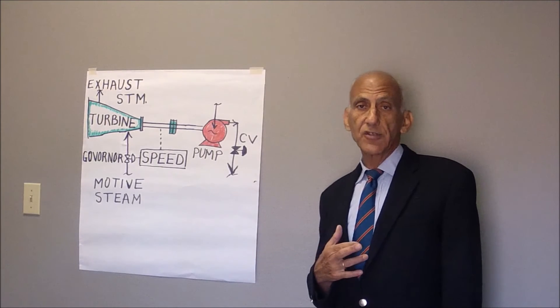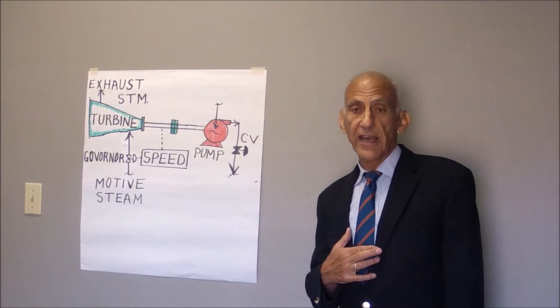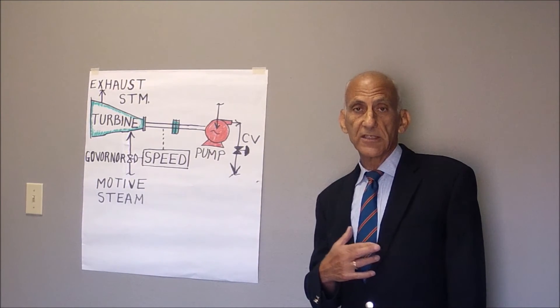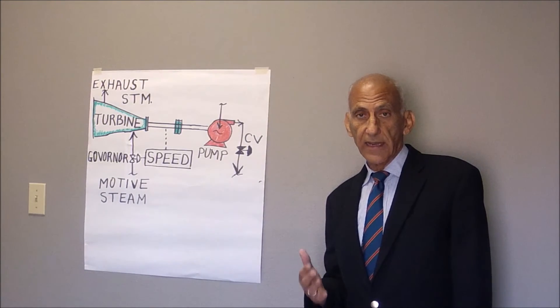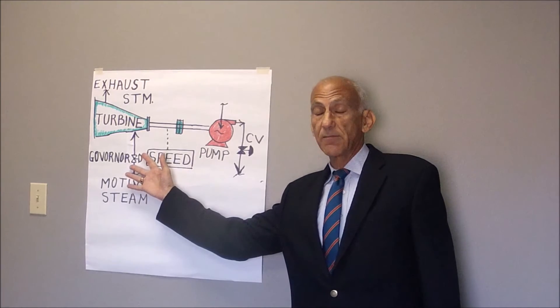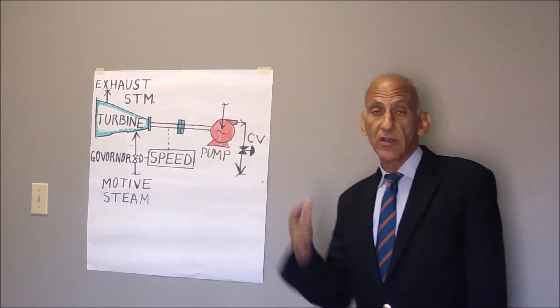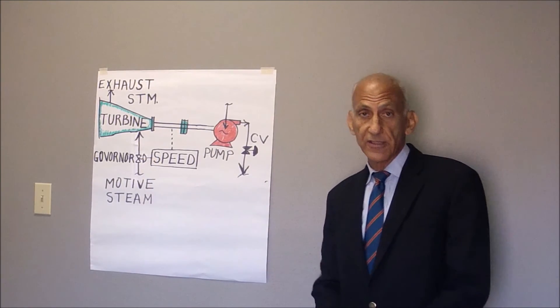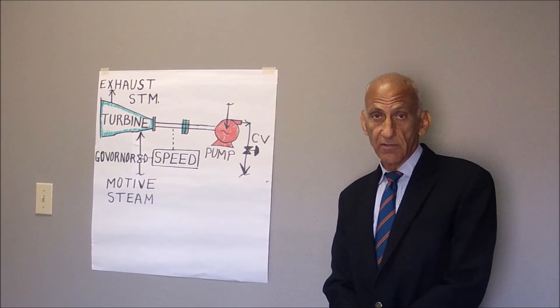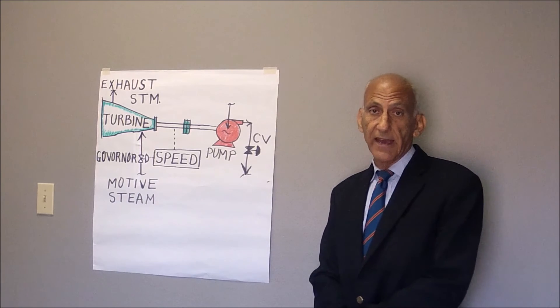And the other thing which may disturb you about what I've just said is because you slow the turbine down, and as a consequence, the governor's steam speed control valve starts to close, reducing the amount of work you could extract from each pound of steam, because you are parasitically throttling the steam back.